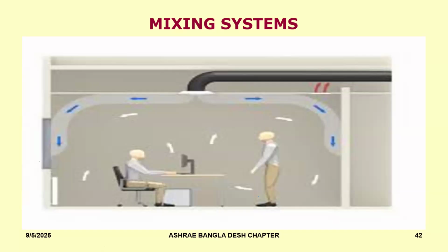Identify where the loads are located, where people are sitting, and then decide where you should place your supply air outlets. And then make sure that the return air inlets are located such that there is good mixing and ventilation in the entire space.